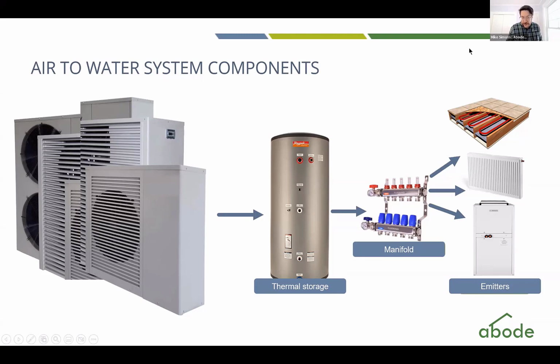When you're calling for heat inside the home—say you have radiant floors, which want to be around 90 degrees—the radiant floor zone calls, and through a circulator pump, energy from this thermal storage tank flows into the radiant floors. If 90 degree water came in and 75 degree water came out, that 75 degree water goes back into the thermal storage tank to be reheated by the air to water heat pump system.